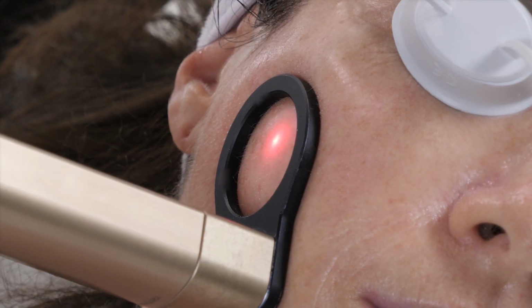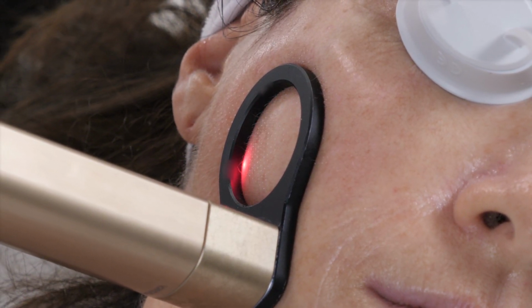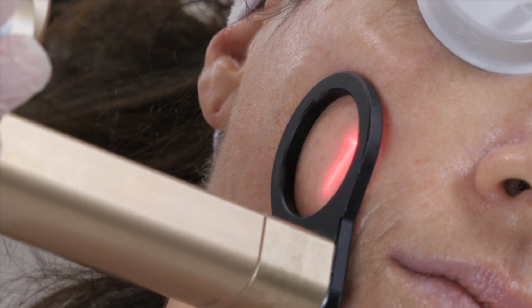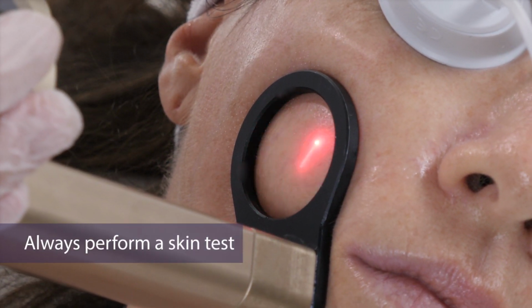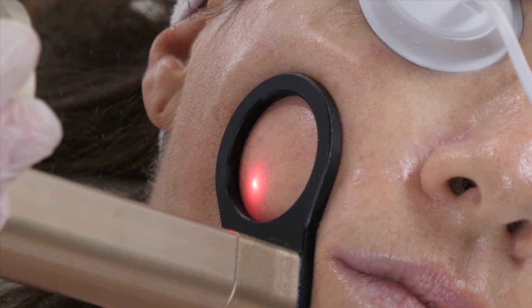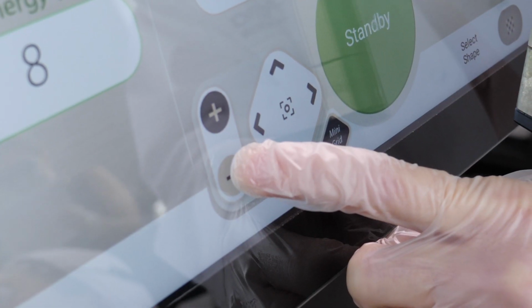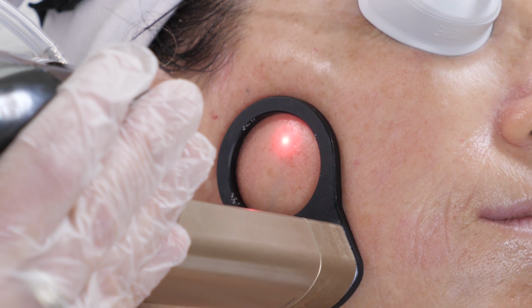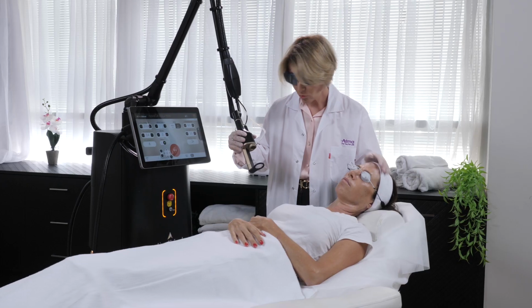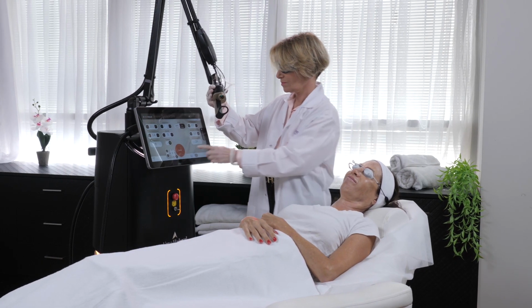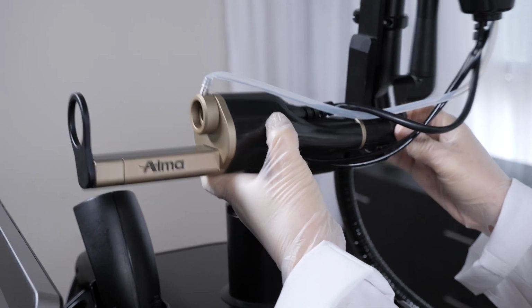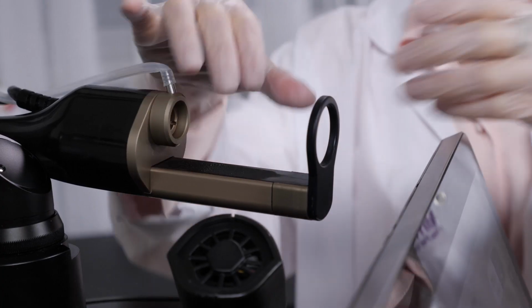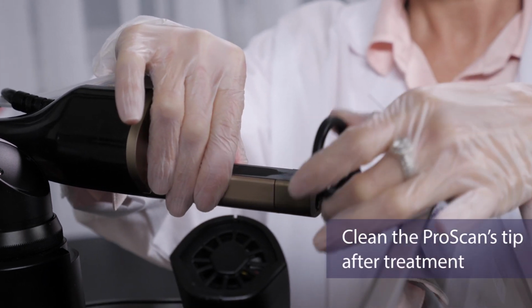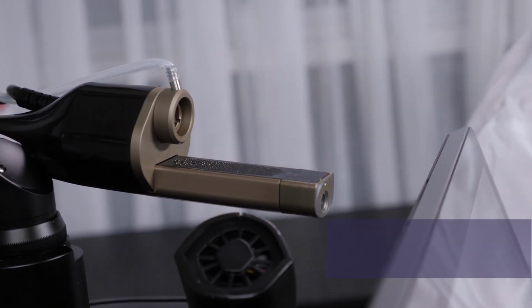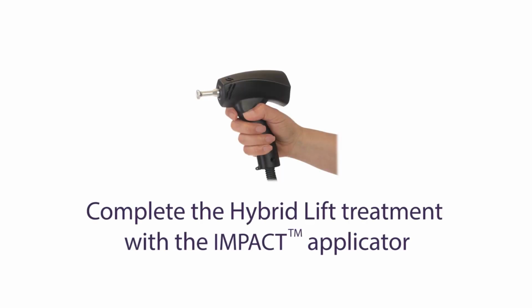For ideal coverage, space the scanning areas next to each other with no overlap. Always perform a skin test. Change the size of the scanning area as needed. Upon completion, switch back to Standby mode by pressing the Ready button. Detach the cooling tip by turning it 45 degrees clockwise and clean the applicator according to the operating manual's cleaning instructions. Complete the hybrid lift treatment with the impact applicator.